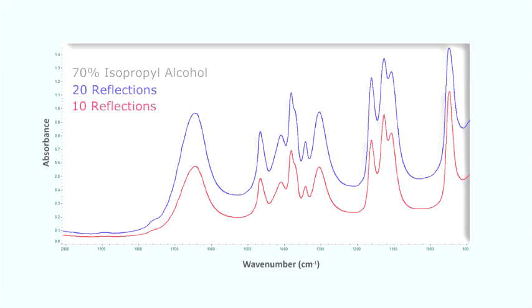Let's compare spectra collected with Pike's HATR 10 and 20 reflection zinc selenide plates. The sample is 70% isopropyl alcohol. The absorbance bands increase by a factor of 2 when doubling the number of reflections.